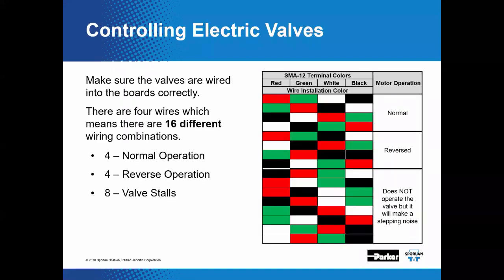Now here, we said something about this just on the previous slide. Reversing the sequence causes the valve to close versus open. This chart actually depicts what happens for all the different combinations of lead wire termination, ranging from normal operation to reverse operation to simply no operation. And you can see that's depicted here, right?